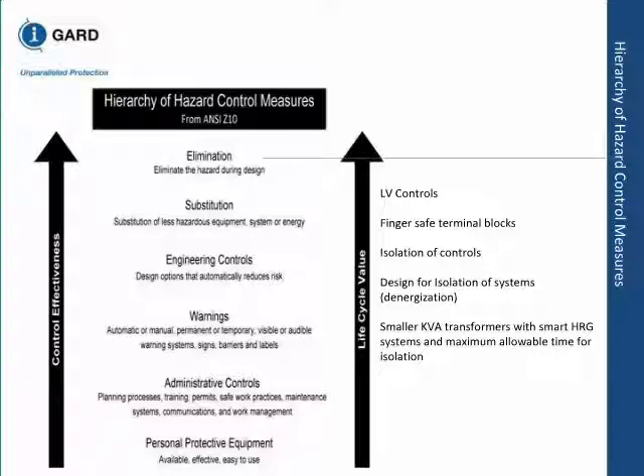One common thing you can do during the design stage, and it cannot be done later, is this: if you have different voltages in the system, for example, you may have a 480 volt breaker in the same compartment as 120 volt control, you can isolate them so they are in different compartments. So when somebody is working on low voltage, they are not exposed to higher voltages. Now keep that in mind. All this does is give you shock protection, unless both cubicles are arc resistant.